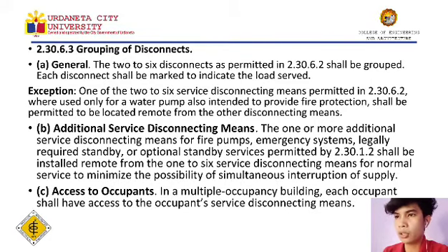And the second is additional service disconnecting means. The one or more additional service disconnecting means for fire pumps, emergency systems, legally required standby or optional standby services permitted by 2.30.1.2 shall be installed remote from the 1 to 6 service disconnecting means for normal service to minimize the possibility of simultaneous interruption of supply.